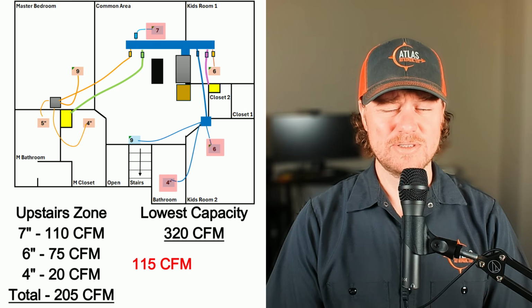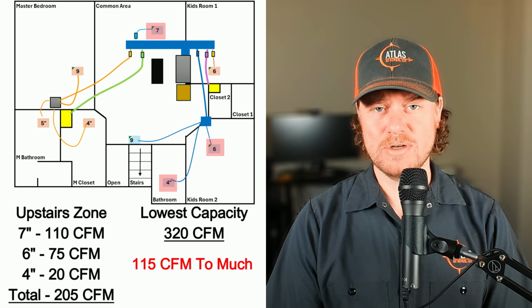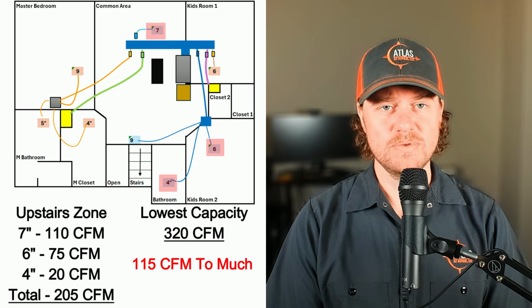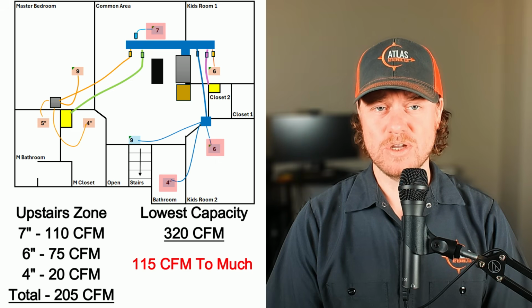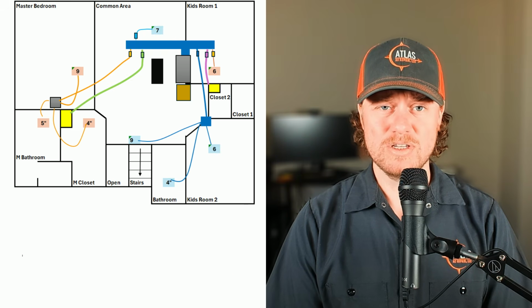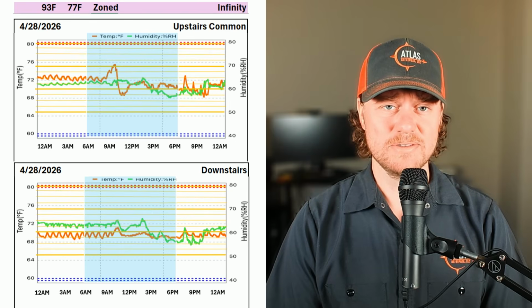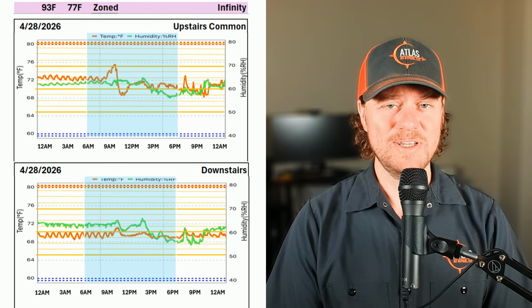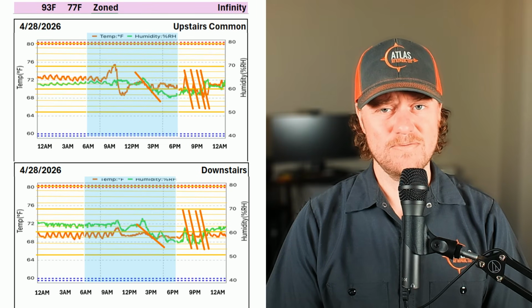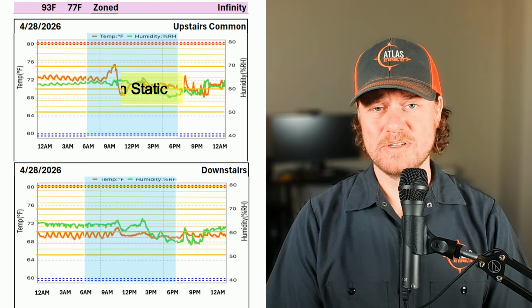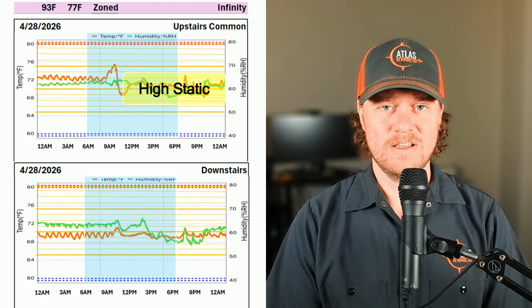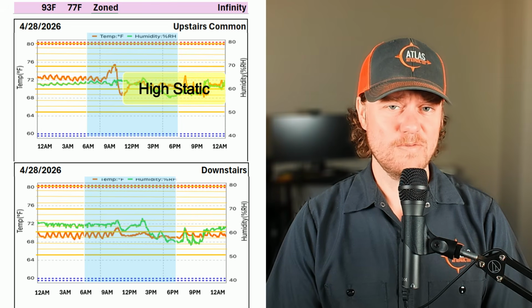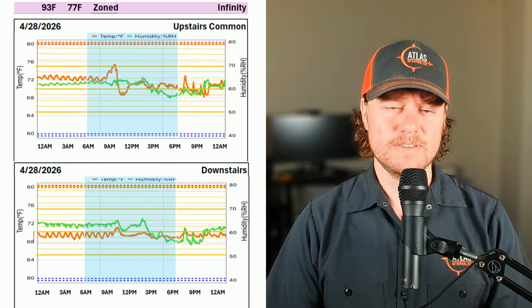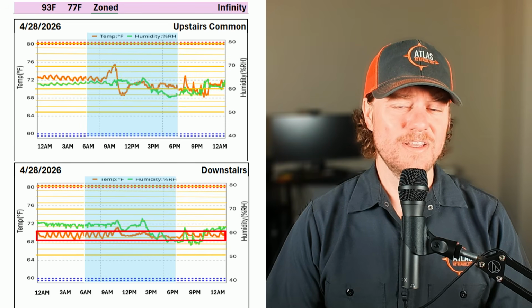What's happening here is this zone is now creating a lot of static pressure. However, the Infinity system should be smart enough to open up some of the other zones in order to reduce this static pressure buildup. And if we take a look at the downstairs data logger, we can see that it is bleeding some to the downstairs, but not very much. So what's happening here is the upstairs zone is maintaining high static, and the Infinity system is only bleeding off the bare minimum. And the reason for this, the system is trying not to overcool any of the other zones.